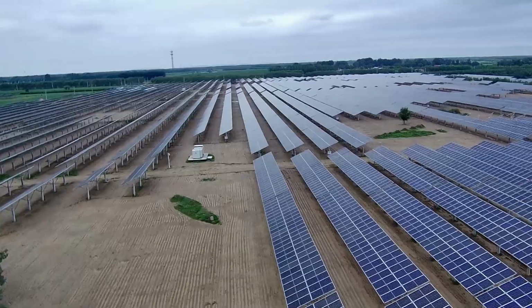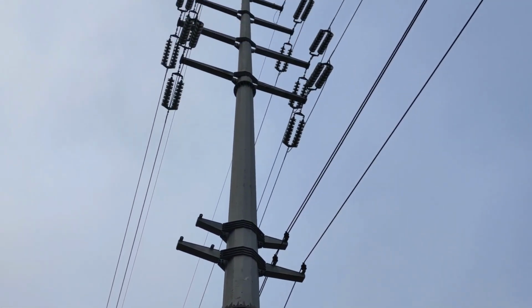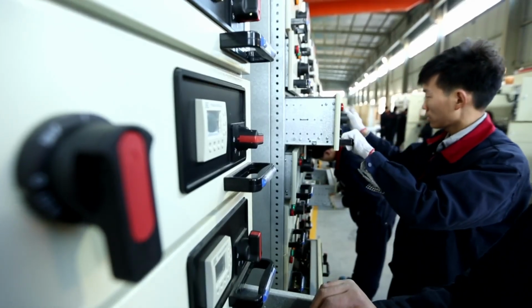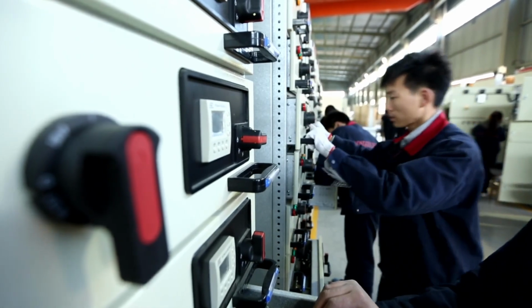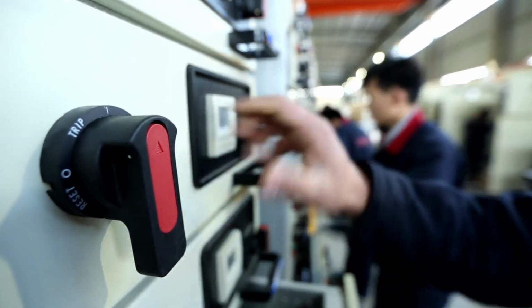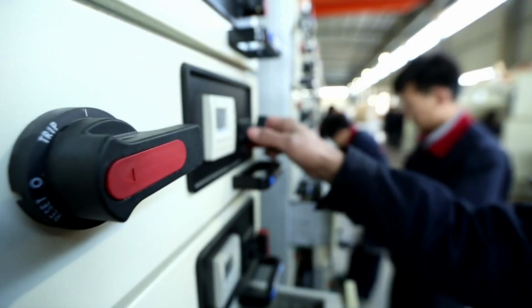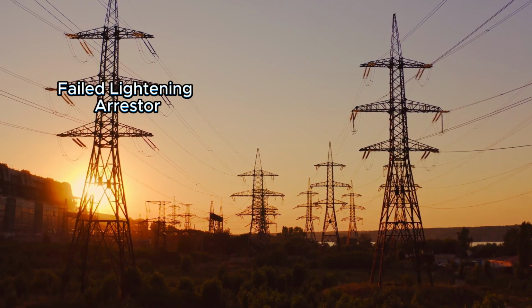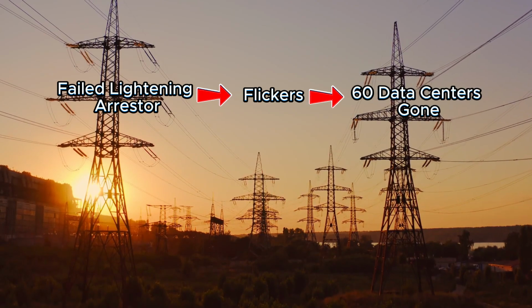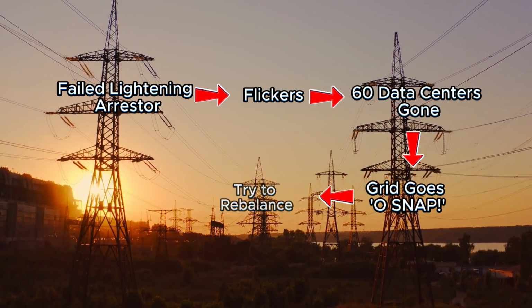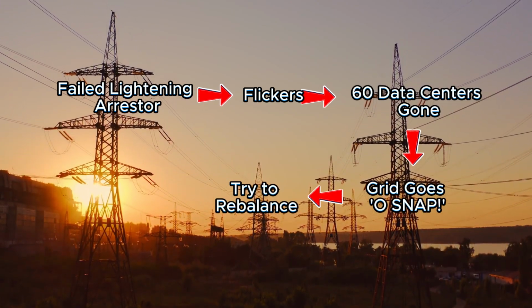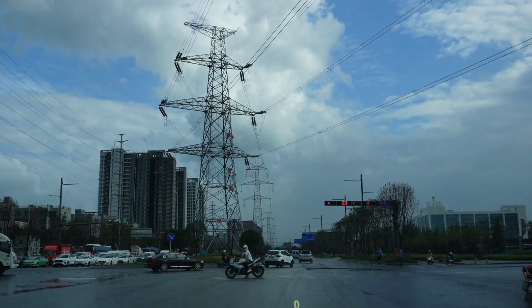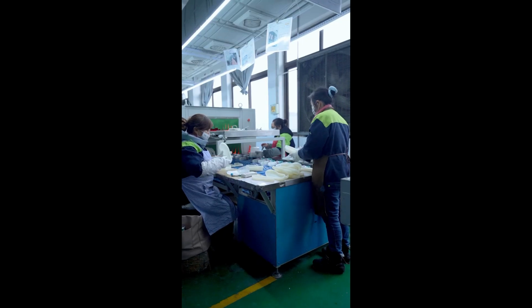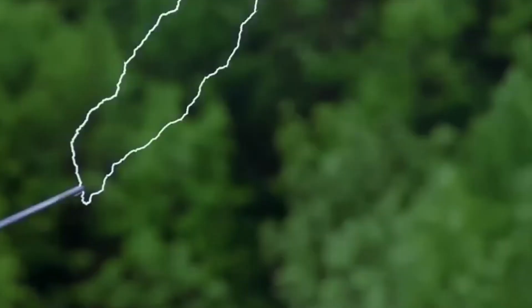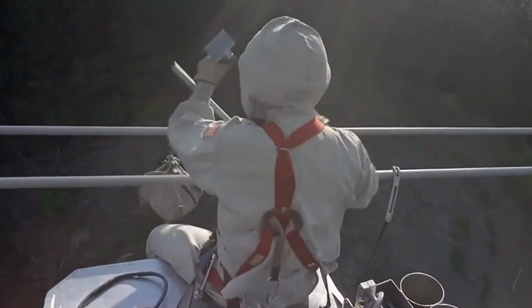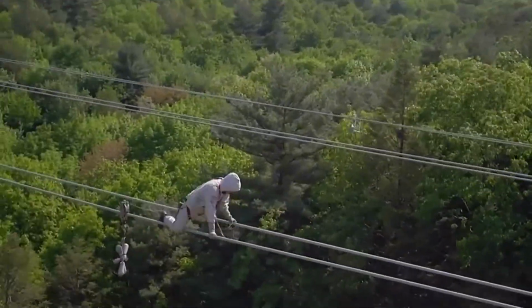Now, the grid needs to maintain that balance between demand and supply of energy. With 1500 megawatt of energy out from the grid, they need to reduce the supply, else it might blow up the fuses and breakers due to excessive supply. So yeah, a failed lightning arrestor, millisecond flickers, 60 data centers gone, grid goes oh snap and scrambles to rebalance. All this from a lightning arrestor that didn't do its job. It wasn't something the grid was built to expect. Operators have always planned for a big generation drop offline, but not like this. Definitely not 1500 megawatt at once.